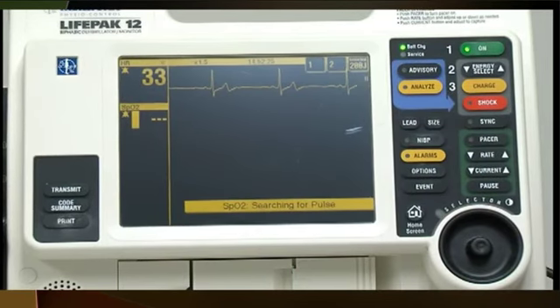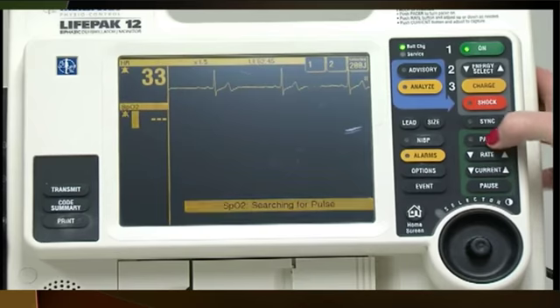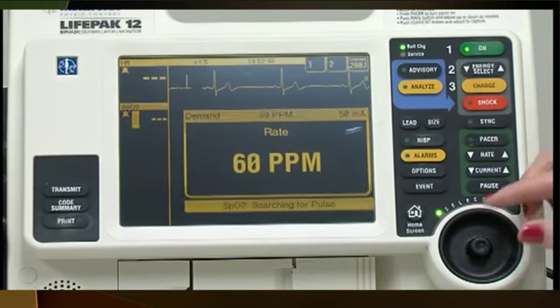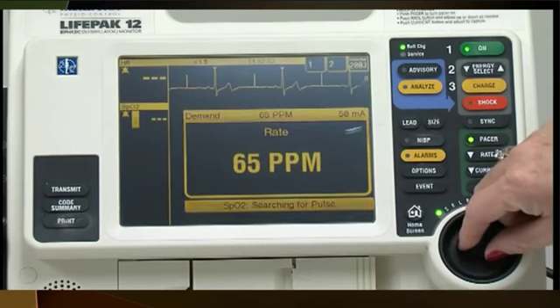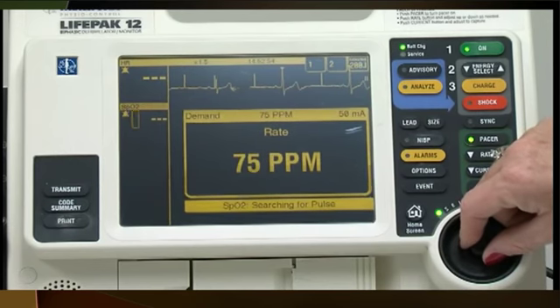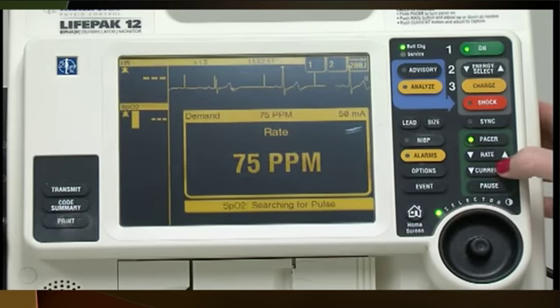Pacemaker stimulation threshold. The importance of this is to make sure that the tissue that the pacemaker leads are attached to is able to be stimulated to cause a contraction. We're going to demonstrate how to do this. First of all, you have a patient whose heart rate is low. We need to increase it. We're going to turn on our pacemaker. With this, you need to increase your rate until the pacemaker has 1-to-1 capture. I'm going to go up to about 75.